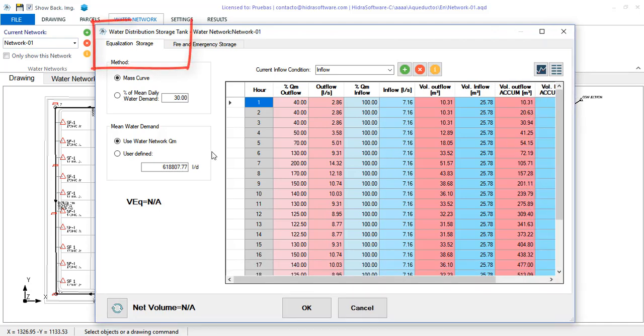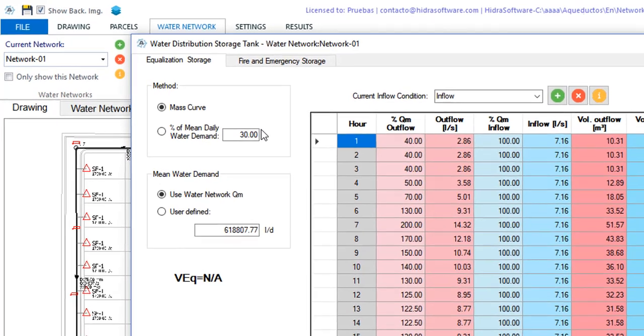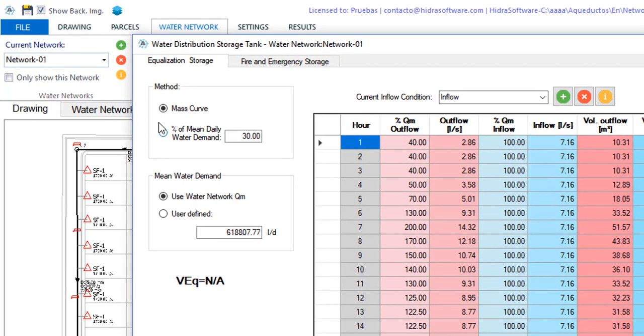Here you will see in the equalization storage tab a box with a method of calculation of this volume can be selected. By default the mass curve method is active. In this method the amount of equalization storage required is obtained through the comparison of the production rates with a typical day demand pattern. The area between the respective curves will be the equalization storage.